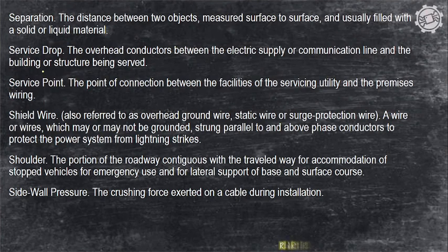Okay, separation, the distance between two objects, measured surface to surface, and usually filled with a solid or liquid material. Then, service drop, the overhead conductors between the electrical supply equipment or communication line and the building structure or structure being served. So, service drop, nasa taas. Service lateral, nasa baba. Yun yung dalawang pagkakaiba. Service drop overhead conductors, either for electrical supply or communication line. Service point, the point of connection between the facilities of the servicing utility and the premises wiring.